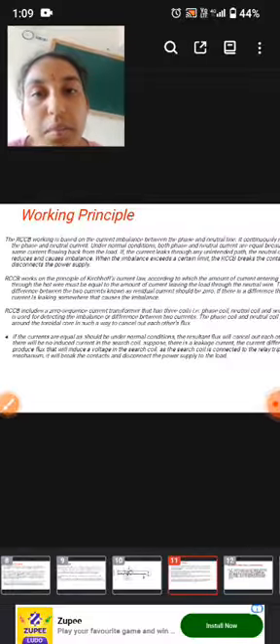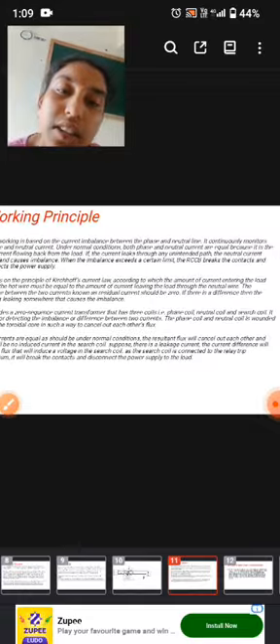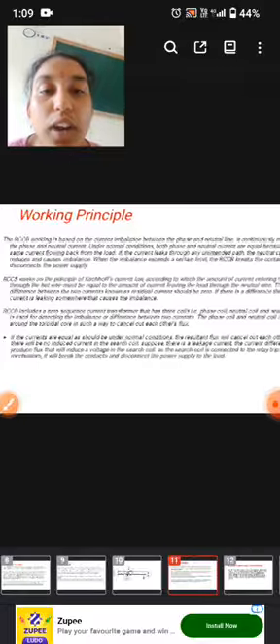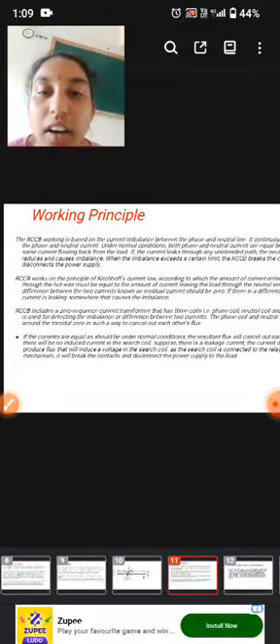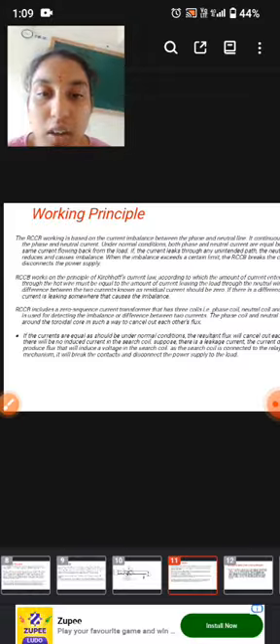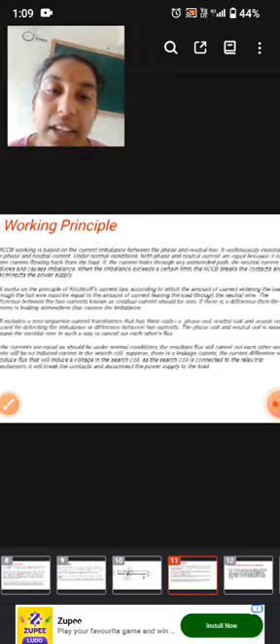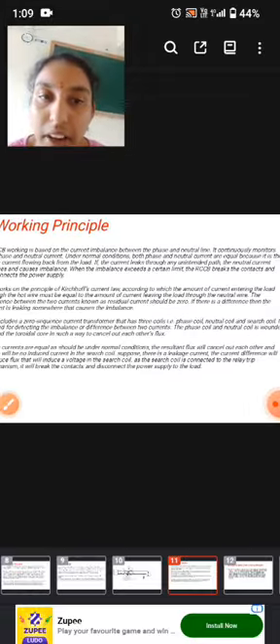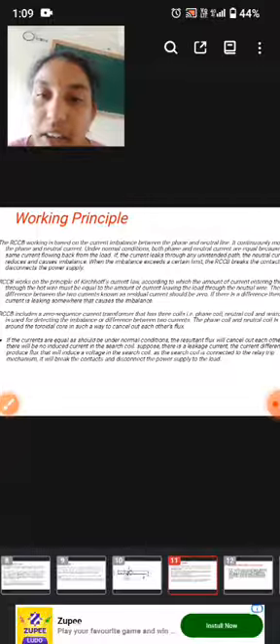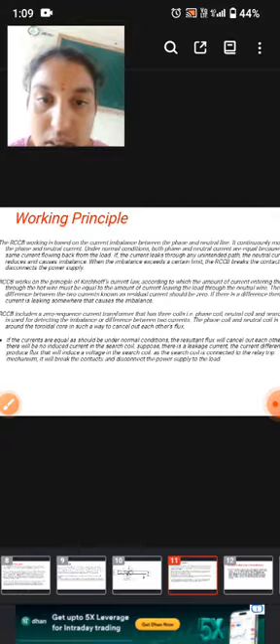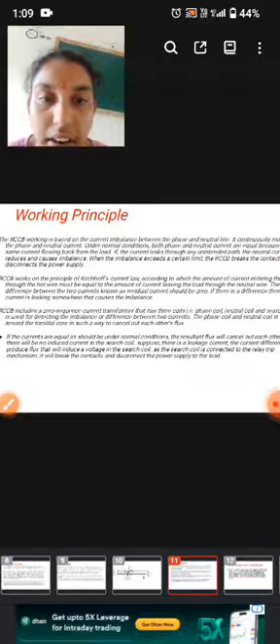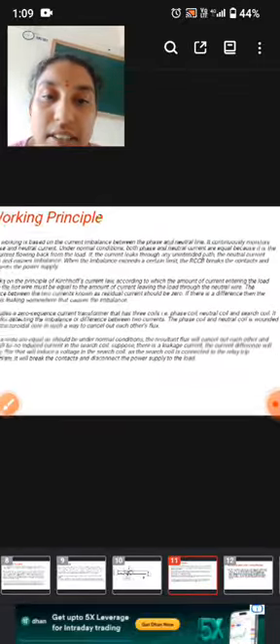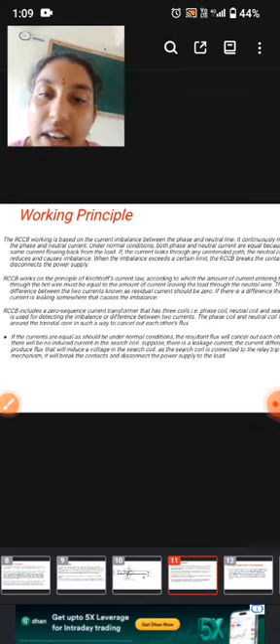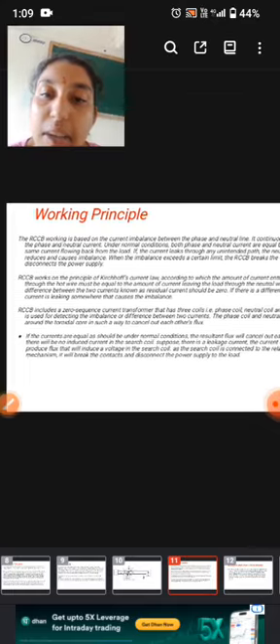RCCB works on the principle of Kirchhoff's current law. According to this, the amount of current flowing to the load through the hot wire is equal to the amount of current leaving the load through the neutral wire. The difference between the two currents is known as residual current, and it should be zero. If there is a difference, then current is leaking somewhere, which causes an imbalance.